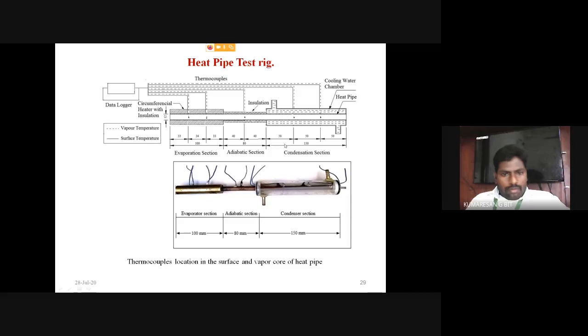There is a concept while fixing the evaporator and condenser length of the heat pipe: it should be in a 1:1.5 ratio. So for 100 mm of evaporator length, you have to fix 150 mm of condenser length, or if going with 200 mm, it should be 300 mm. Only then can the heat pipe remove heat continuously and effectively.